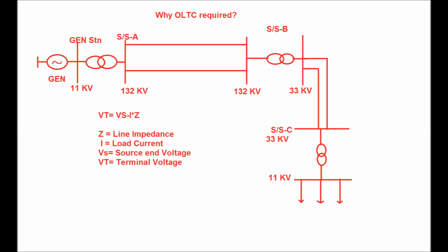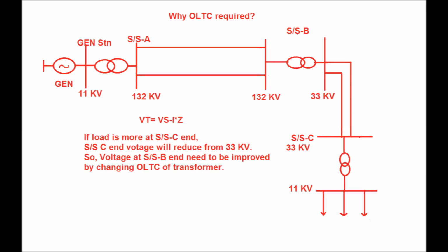So we know that Vt is equal to Vs minus I into Z, where Z is the line impedance, I is the load current, Vs is the source end voltage and Vt is the terminal end voltage. So if the load current increases, then there will be more drop in the line, and therefore the terminal end voltage will decrease. So during a heavily loaded condition, for example, if the 11 kV feeder is heavily loaded, then the 11 kV terminal end voltage at the pole mounted substation will decrease, and again at substation C end the 33 kV voltage will decrease. So in case of a distribution substation, there is no provision for an on load tap changer, so the tap must be increased from the substation B end or grid substation end.